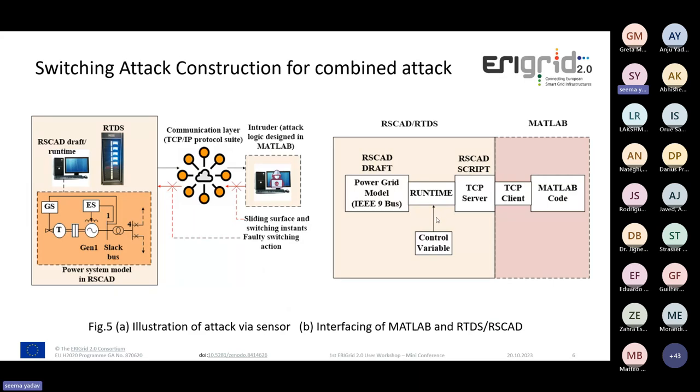The switching attack construction for combined attack, which I have implemented in the VTT, was based on trying to imitate the intruder behavior. For that we have used RTDS with RSCAD installed in one system, and another system with the attack logic designed in MATLAB, which acts as an intruder. We have used the TCP/IP protocol to communicate between RSCAD and the intruder's switching logic.